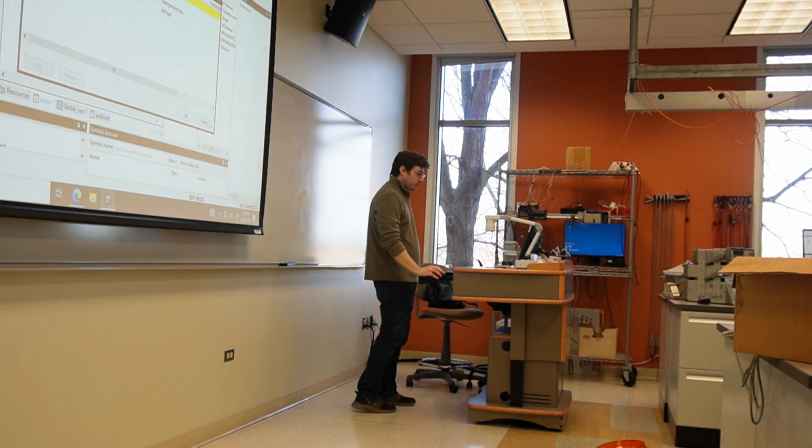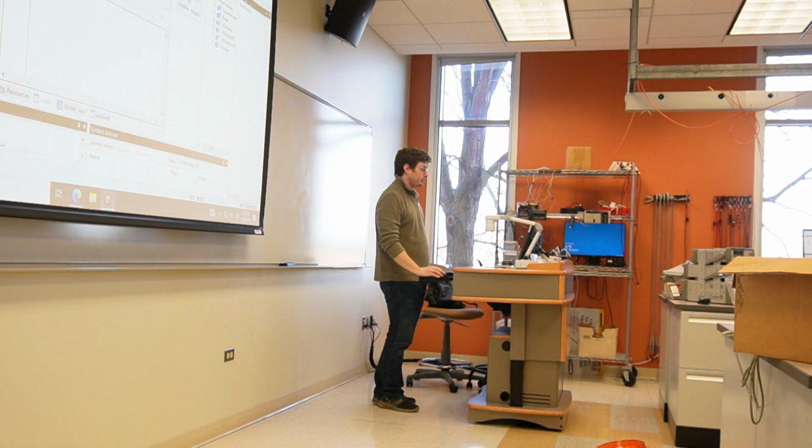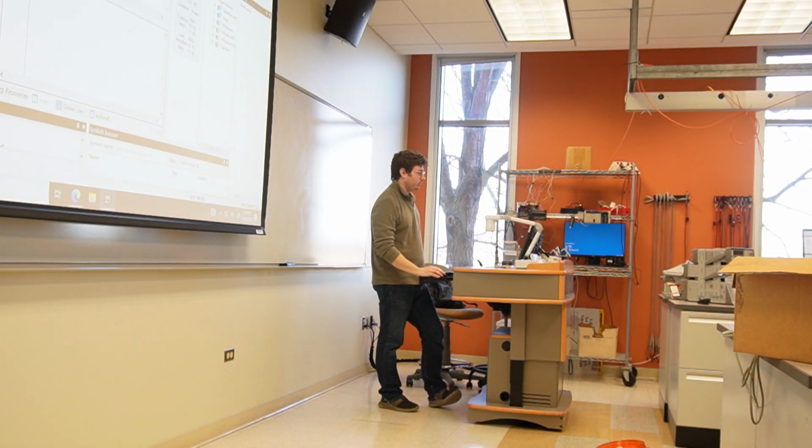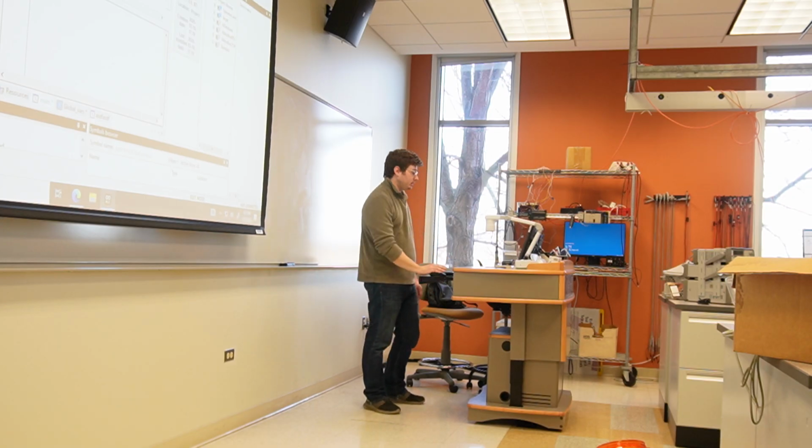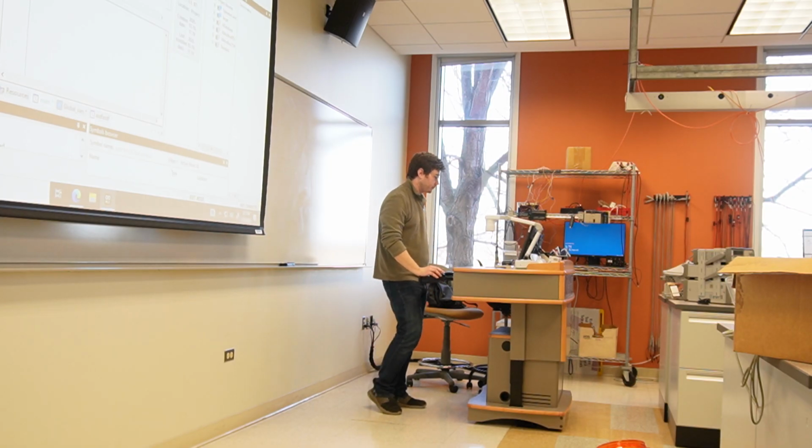Extremely important, again, for when we're debugging is to make sure that if you create a new program, it's within your fast task group, okay? Because if it's not, like I said, it won't do anything. You'll run it all day and nothing will happen and you'll wonder why. Okay, so if I were to remove that for some reason, I just clicked on it and pressed delete, you can still really easily assign that task, okay?